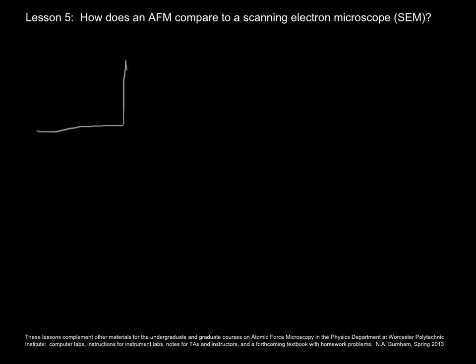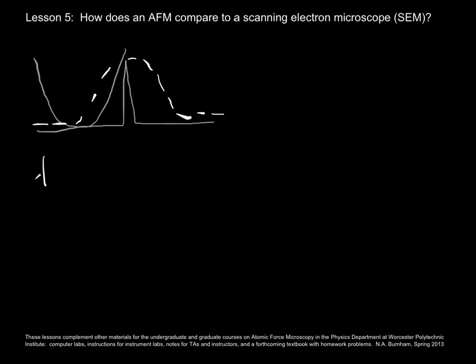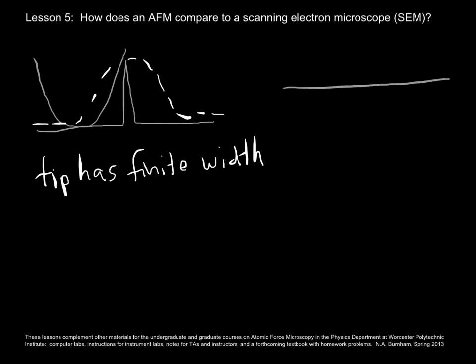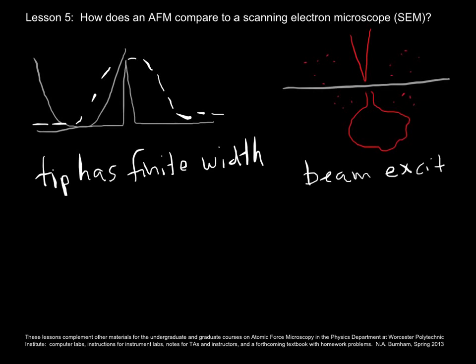Let's do a side-by-side comparison. If we have an AFM sample with a sharp feature and our AFM tip in contact, as that tip passes over the feature, the path it follows will be broadened because the tip has finite width. In the scanning electron microscope, there's an equivalent phenomenon — the beam excites a finite-width bulb of volume, and some of the lower-energy electrons make it to the surface and are collected. So the beam excites a finite width, which is equivalent.